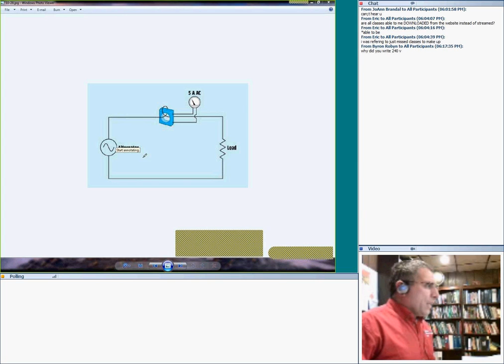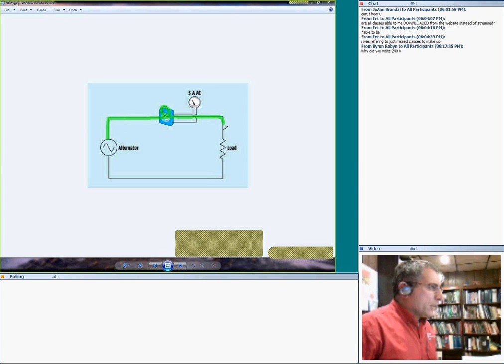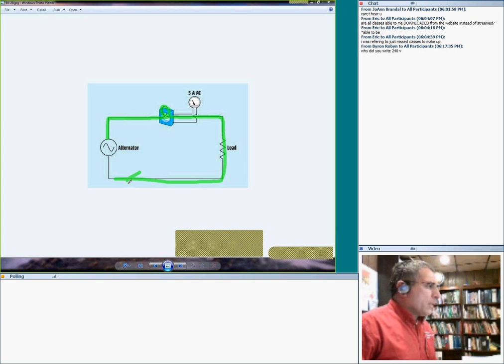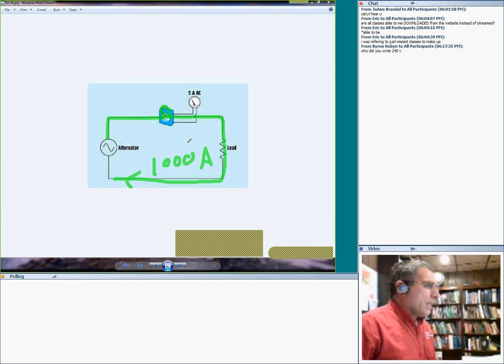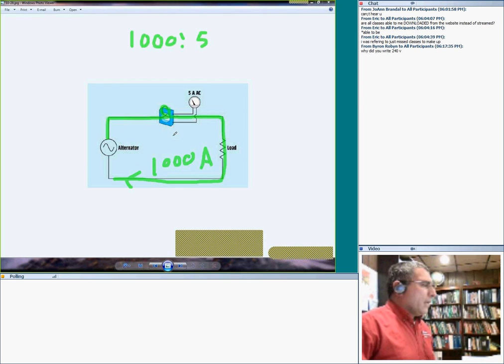Suppose they looped the wire 2 turns inside the CT instead of just passing it through once. Now the current goes through twice. So the current here was 1000 amps going through the whole system. If you loop it, this CT, which was rated 1000 to 5, now has 2 turns, so it becomes 500. If it's 3 turns, you divide the 1000 by 3.